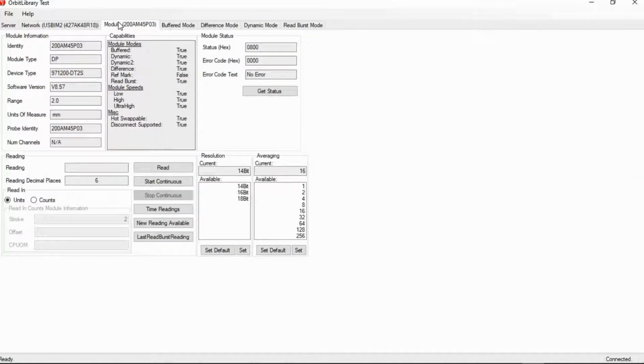Click Module. And if you'll see here, this gives all the particular information about this particular digital probe. Here's its identity, module type, DP. Here's the part number, 971-200-DT2S. The software version. This actually means the firmware version that is loaded onto the Orbit module itself. Measurement range, and units measured. And then it shows the different capabilities. It can run in dynamic, dynamic 2, as well as read burst. Then there's a couple of simple features.